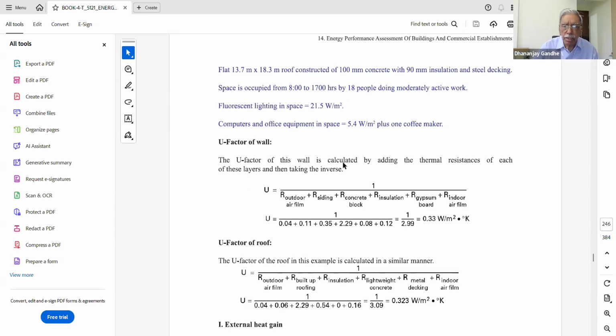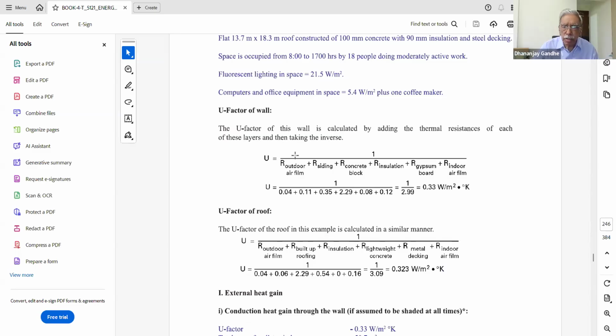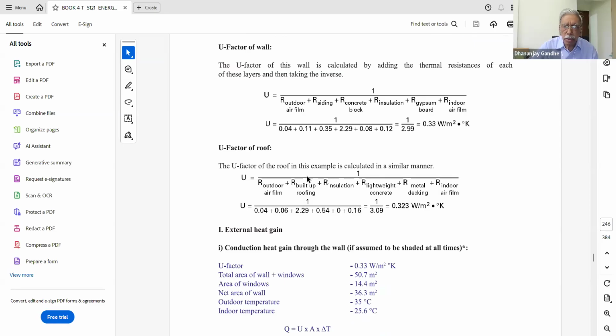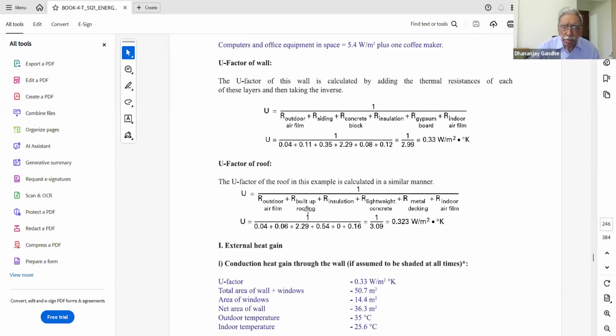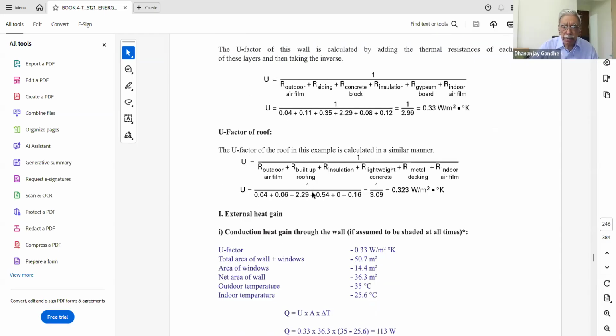We are supposed to calculate the heating load. So the U factor of the wall, how to calculate it for the entire wall. So the wall consists of, also the siding. It consists of concrete blocks, insulation, indoor air film, outdoor air film. So the composite U factor, how to calculate it, is given here. The roof also is given here, because the same parameters will be there, that will be the insulation provided by the roof slab, and there will be concrete and so on. So this can be calculated with the help of an architect also. It can be calculated. Okay.